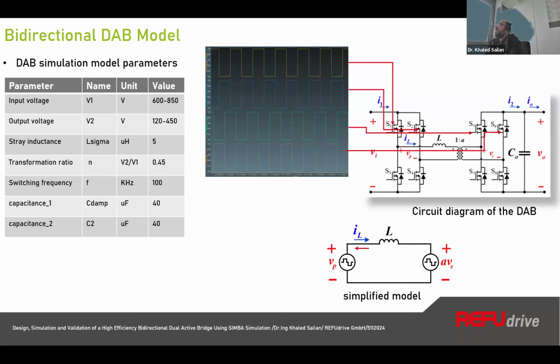Just the signal on switch 5 has been shifted with the phase shift from 0 to 90. Depends on your power flow. If you would like maximum power flow, you can apply 90-degree on switch 5 or in the secondary side with respect to the primary side. But for our application, because we would like to run with high efficiency over 98%, we decided to go with triple phase shift.